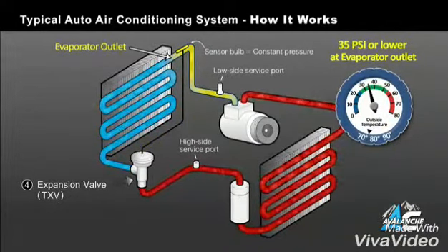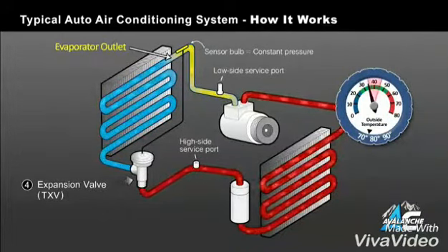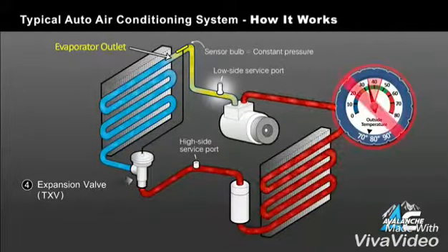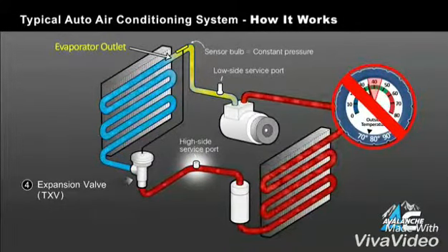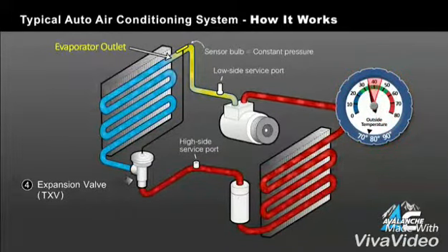If this pressure level is below the gauge's established correct fill, which is typically over 35 psi, even though the system is fully charged, adding additional refrigerant will not show on the low side pressure gauge, but will build up on the high side and can only be measured using a high side gauge.